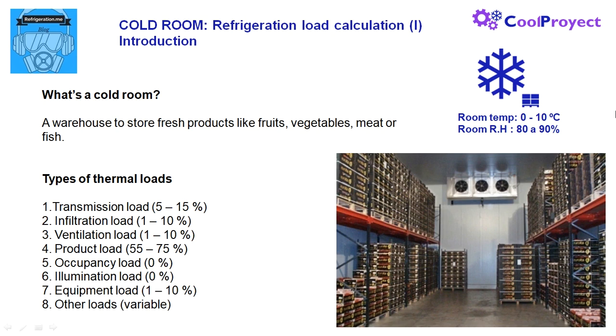Both infiltration and ventilation loads could account for 1 to 10% of the total load. Number four, we have the product load. This is usually the most important load, representing around 55 to 75% of the total. The more information about the product and its management, the more accurate a calculation we can do.